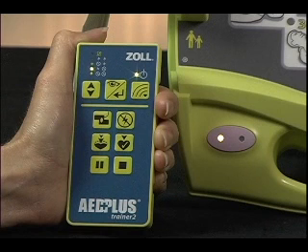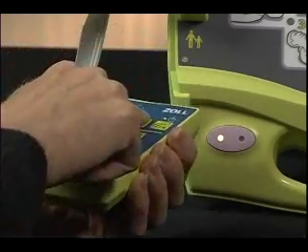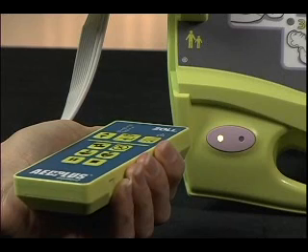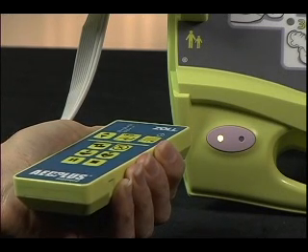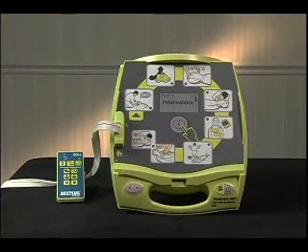Point the remote controller at the Trainer 2 and push the View Enter button a second time to transmit the scenario to it. The red status indicator light will flash once to indicate that the new scenario has been communicated to and accepted by the Trainer 2. This completes the scenario setup.